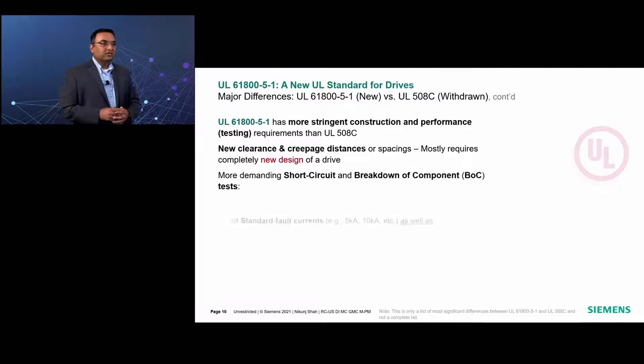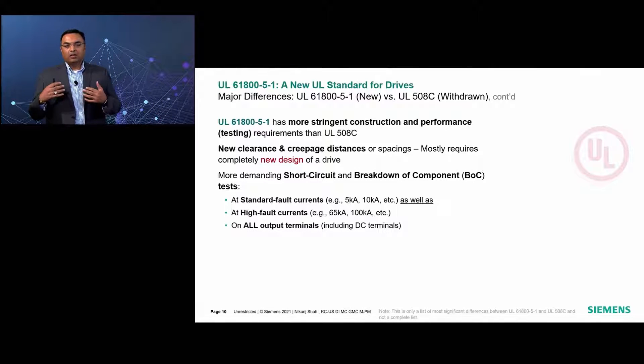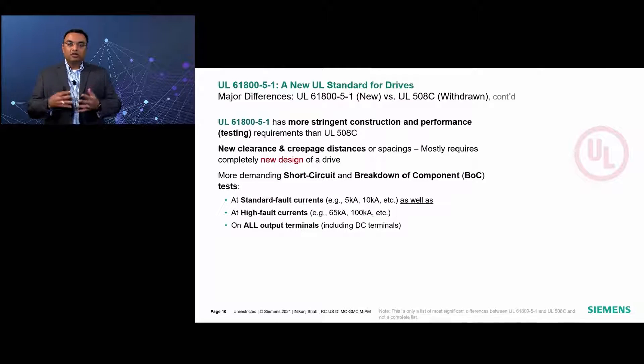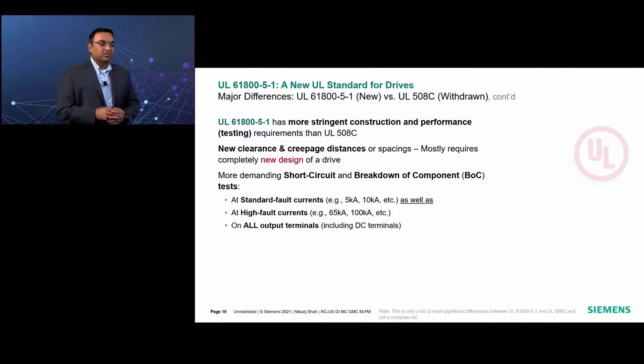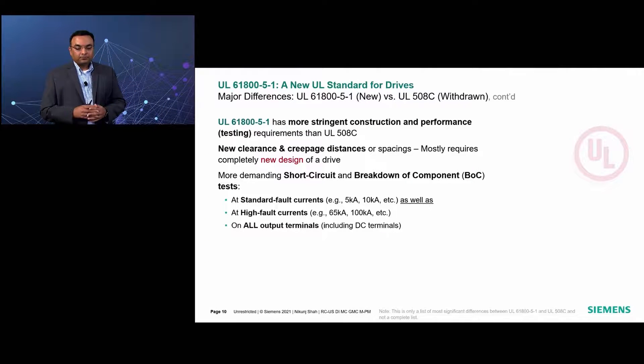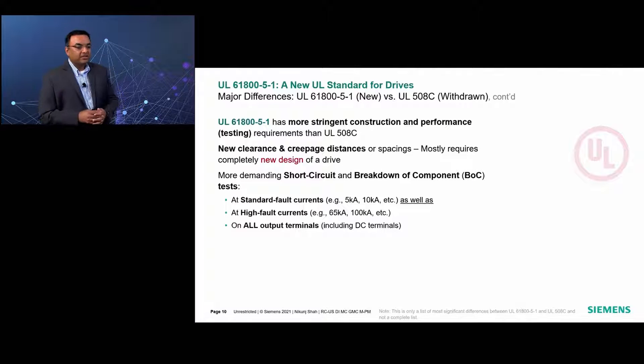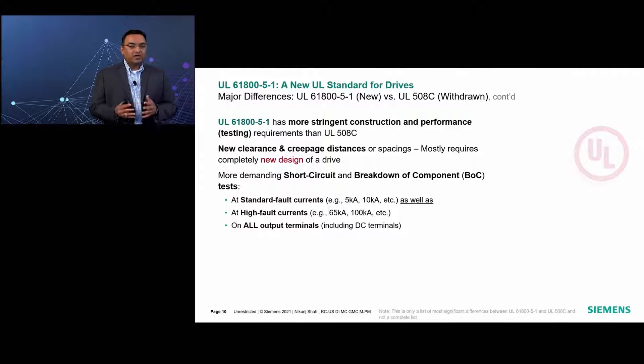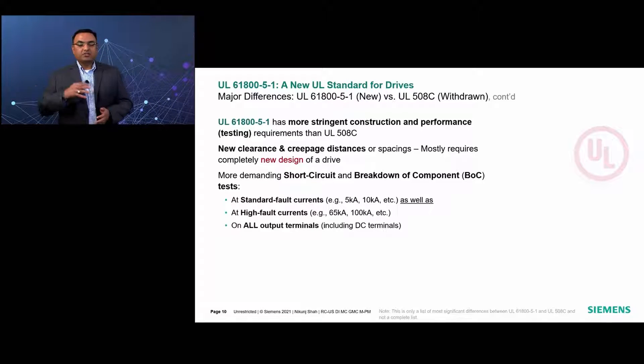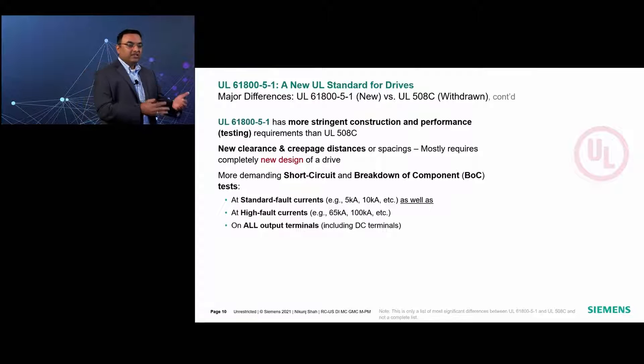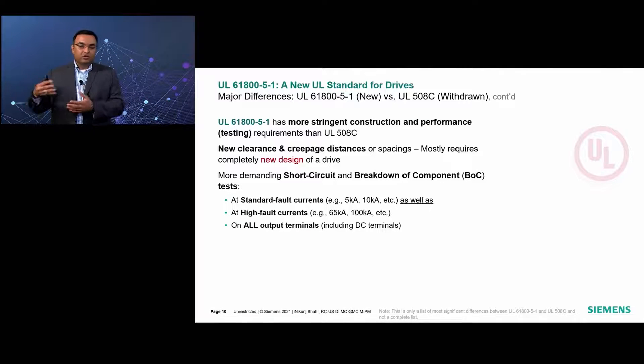Also, similar to this construction requirement, there are more demanding performance and testing requirements added into this new standard to improve product safety of the low-voltage adjustable speed drive. For example, the short circuit test according to 61800-5-1 now requires testing at the standard fault current level — that is 5 or 10 kilo amps — as well as at the high fault current levels, that is 65 or 100 kilo amps, whichever the drive manufacturer assigns to the drive, on all output terminals.